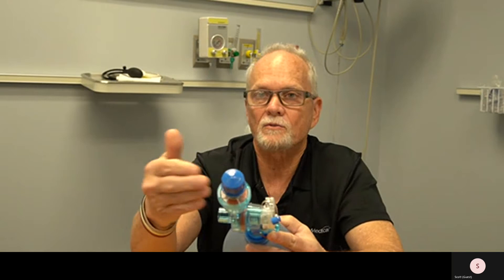This PEEP valve can be screwed out of the bag entirely for zero PEEP. In most places — and I'm not trying to dictate protocol — most places start out at about 5 cmH2O PEEP just to maintain gas exchange and recruit some of the collapsed alveoli. So adding these accessories really shouldn't be optional — physiology is telling me I should be doing smaller volume and I should have a PEEP valve.